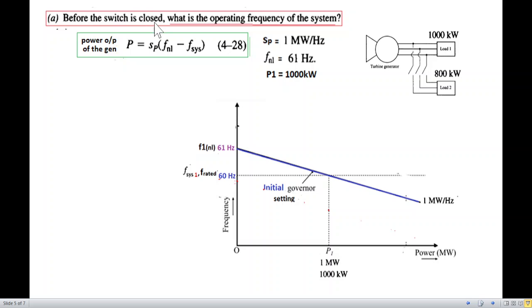Okay, so we'll work with this equation to solve this question. The first part, before the switch is closed, what is the operating frequency of the system? These parameters are given. So first of all, we draw this slope curve. From 61 hertz is the no load. And then the power is given 1 megawatt. So if we take these two points and we draw a line at this point, this will be the slope, which will be at 1 megawatt per hertz. Now, look, when we have 1 megawatt, then the drop here is 1 hertz. So we can say the slope is 1 megawatt per hertz.